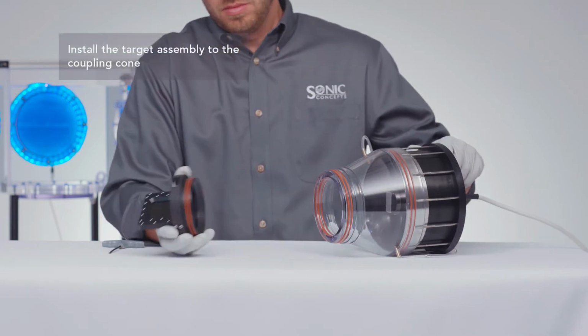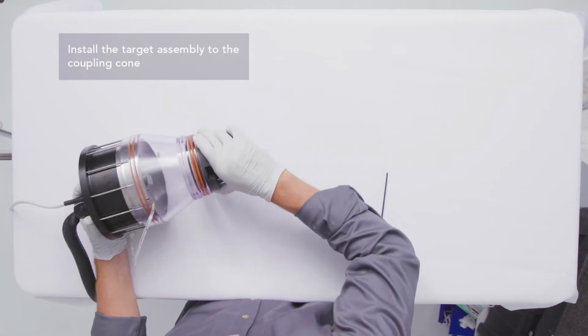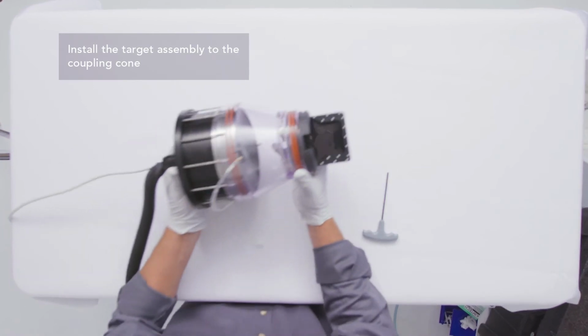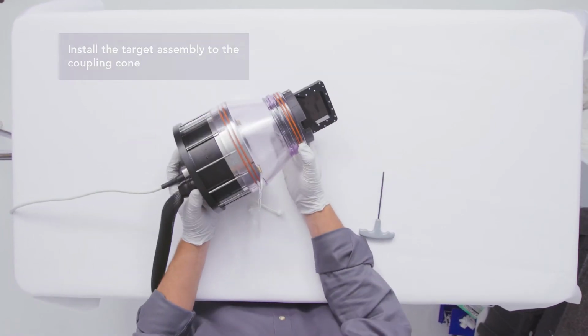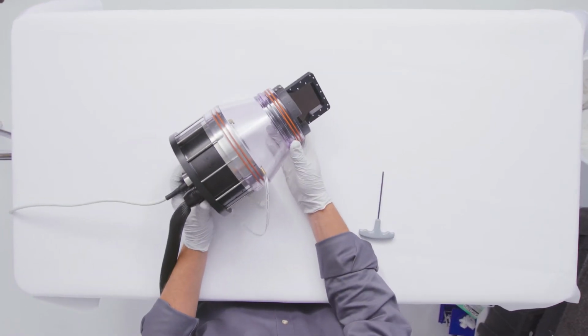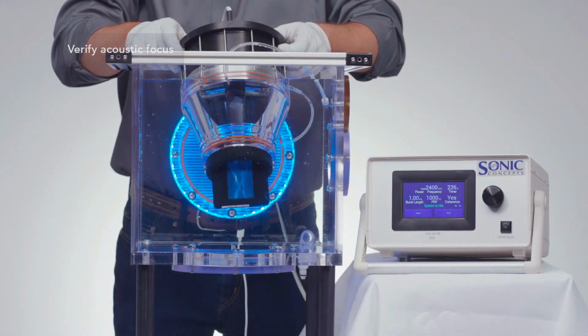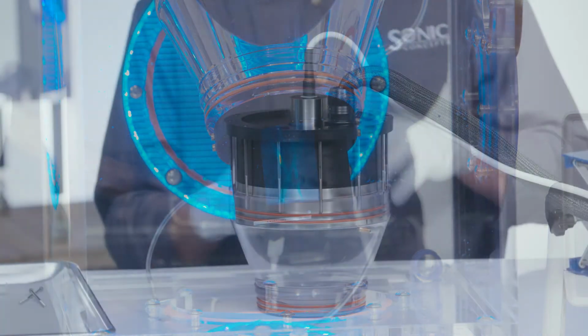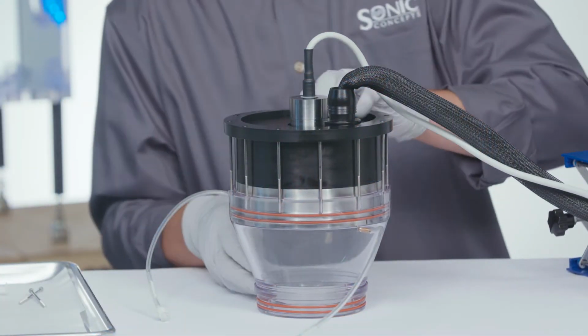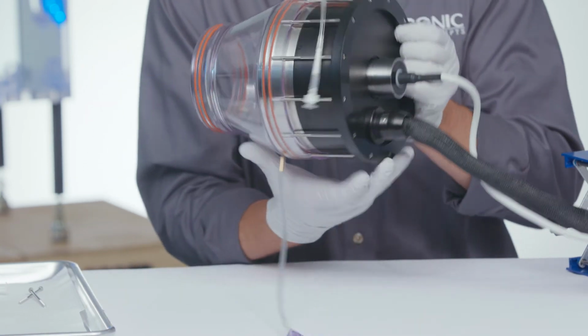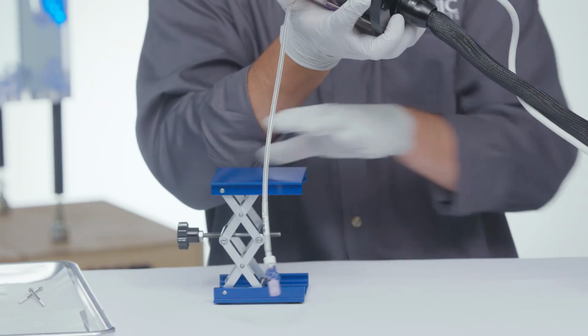The target mount fits onto the cone and aligns the target film with the focal axis. O-ring friction is used to center the mount while enabling the frame to rotate about the focal axis. Using the operating conditions as set forth in the calibration report, verify that the transducer is focusing appropriately. Once the focus is verified, remove the target assembly and prepare to install the coupling membrane.